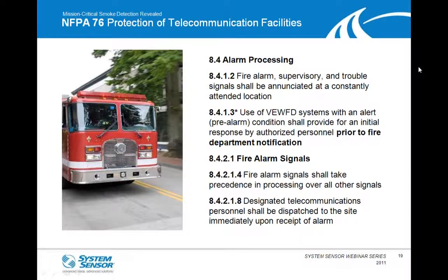So shifting from NFPA 75 into, excuse me, NFPA 76, the first area that we're going to talk about is Section 8.4, which is alarm processing. And what it does call out is that fire alarm supervisory and trouble signals shall be annunciated at a constantly attended location. More specifically, the use of very early warning fire detection, and we'll go into each one of these types of detection levels in forthcoming sections, need to have an alert or a pre-alarm condition.